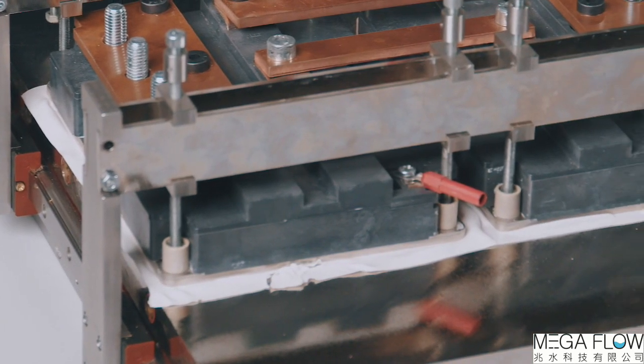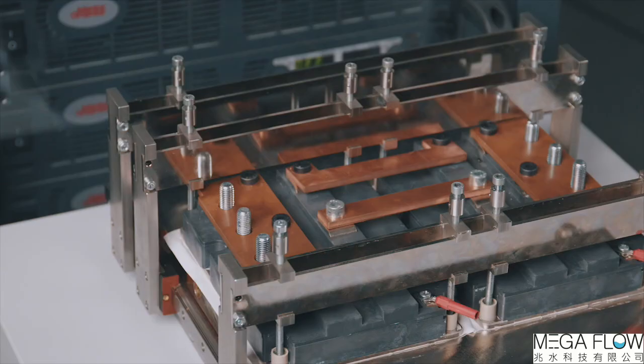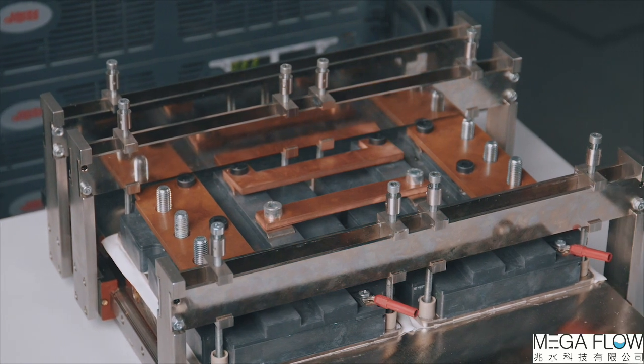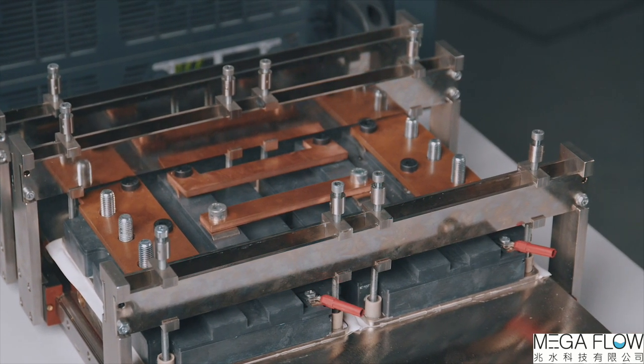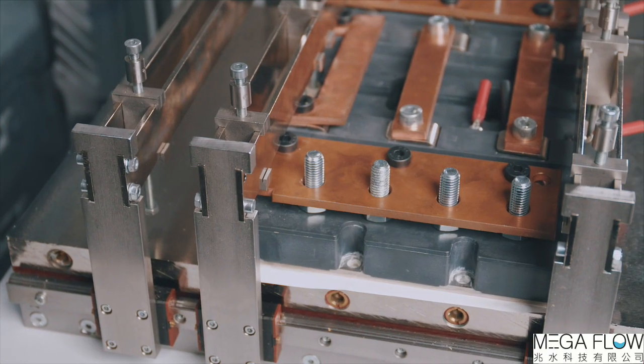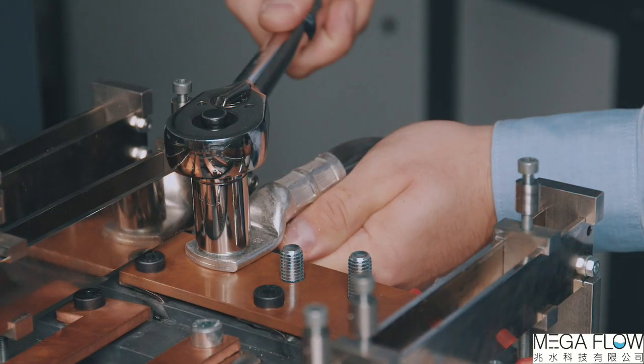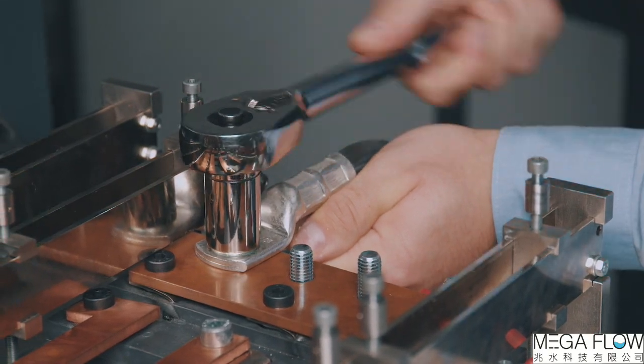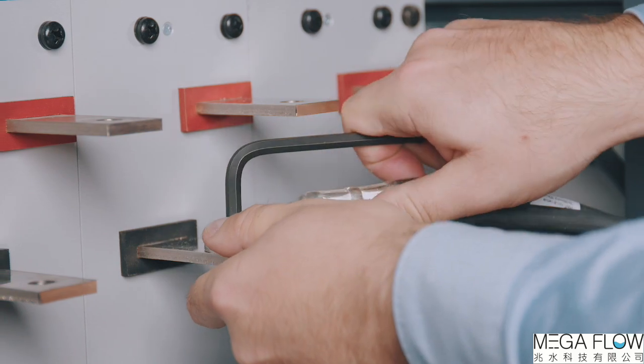The system's primary application is testing silicon and silicon carbide diodes, IGBTs and MOSFETs. Let me show you the measurement workflow for two 2400 amp IGBT devices connected in series. These devices have a classic package with flat cooling surface. We are going to use a cold plate with universal screw fixture to attach the devices. These packages contain a single IGBT transistor each. We are going to connect all the 4 heating current outputs in parallel to supply the required heating power.